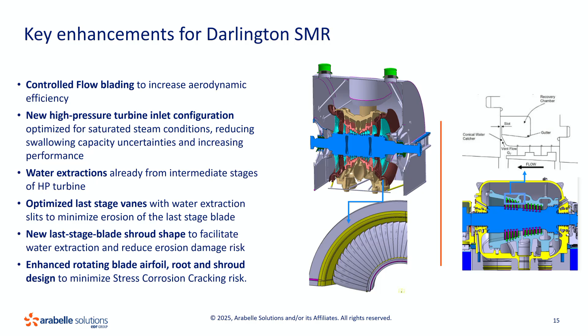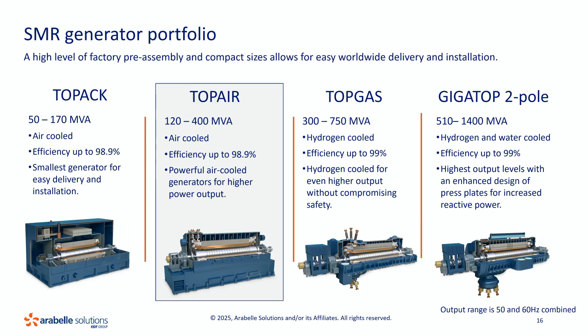I will take the opportunity to show our generators as well. As I said, we have at least 4 types of generator for serving the entire SMR fleet. We have Top-Pack generator, extremely compact, goes in a box, for 50 to 130 megawatt. Then we have Top Air for 120 to 400 megawatt machines, which is being used in Darlington, by the way. It can be pressurized or non-pressurized, depending upon the capability requirement. Then we have Top Gas, which is a hydrogen-cooled generator. And then after that, we have the Gigatop 2-pole, which is a mix of water and hydrogen-cooled.